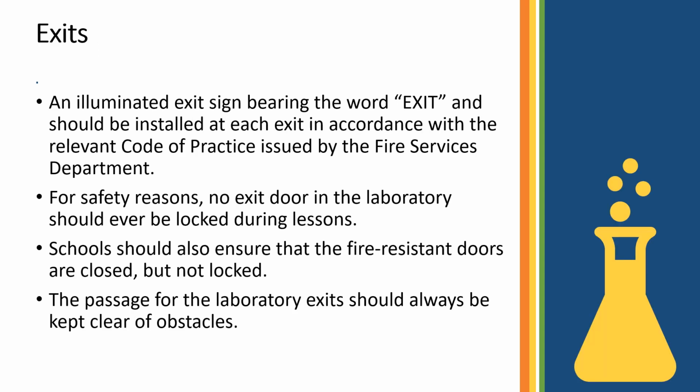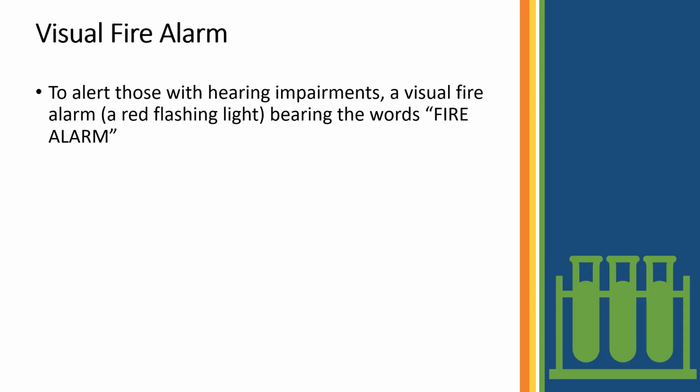Exits. An illuminated exit sign bearing the word exit should be installed at each exit in accordance with the relevant code of practice issued by the Fire Services Department. For safety reasons, no exit door in the laboratory should ever be locked during lessons. Schools should also ensure that the fire-resistant doors are closed but not locked. The passage for the laboratory exit should always be kept clear of obstacles.